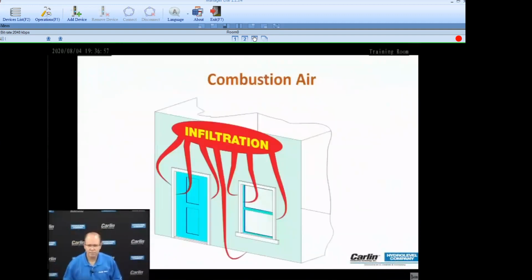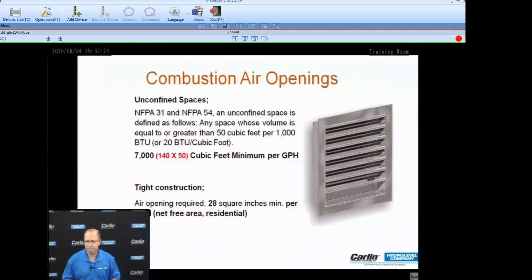It's always when something changes, Angel. Yep. Infiltration for combustion air. Years ago, that was fine. It was reliable. Basements were wide open. They were not finished basements. The equipment wasn't in a closet somewhere or a small equipment room tucked away in the corner. Can't count on infiltration for combustion air.